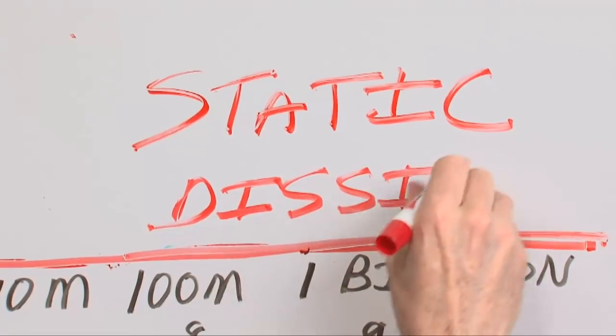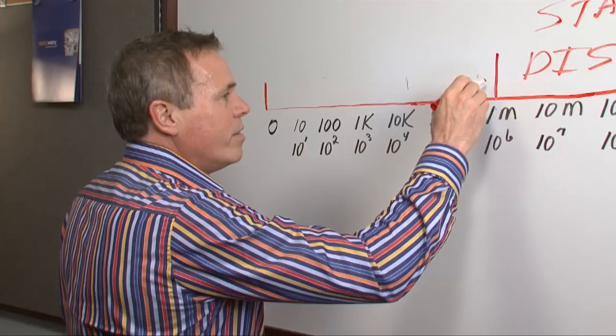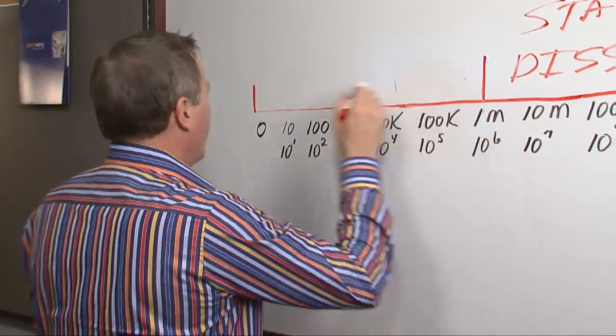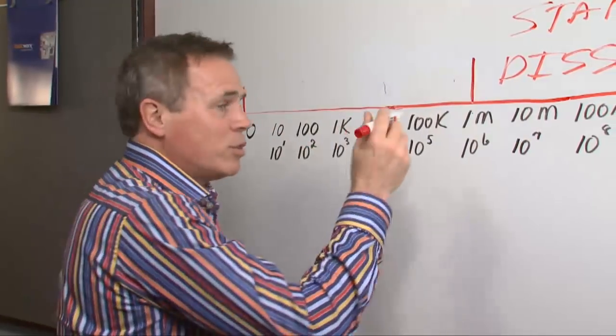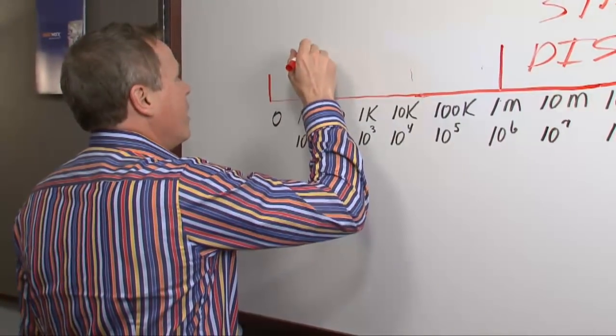If you look up the definition of conductive flooring, you'll determine that any floor that has a resistance of a million ohms or less, and by the way, they don't specify the low number, anything from a million ohms or less is static conductive.